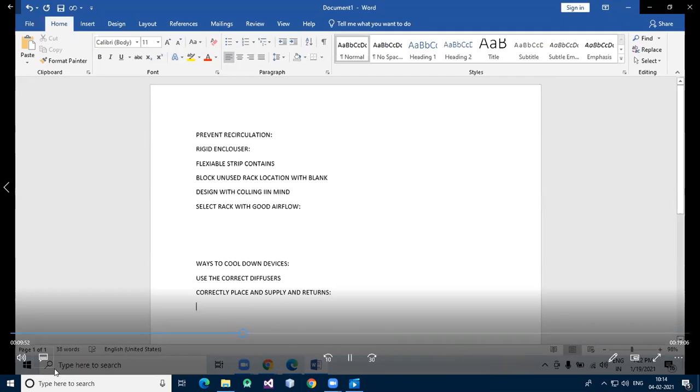So here, diffusers should be placed right by the equipment to be cooled. They should not be placed so they direct cooling air at the heat exhaust, but rather into the air intake. Supplies and slotted floor tiles should not be placed near returns, to prevent cool air short circuits. Minimize air leaks. Systems that use a raised floor can lose cool air through cable access in hot aisles. Optimize air conditioner placement.